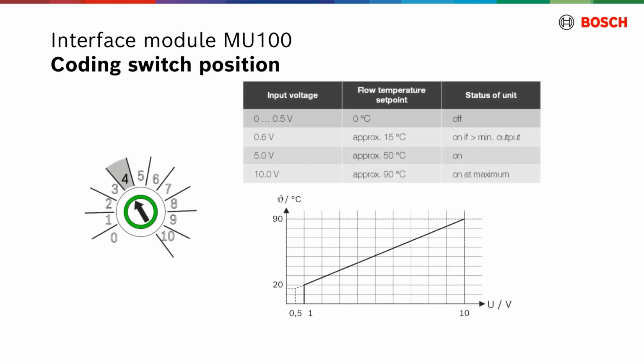With the coding switch in position 4, the module MU100 controls the flow temperature of the boiler. The connected heat source is enabled and disabled according to the signal from BMS and the required flow temperature. There is a linear relationship between the 0 to 10 volt input signal from BMS and the required flow temperature of the boiler. This varies in the temperature range from minimum to the maximum flow temperature set up in the boiler settings, by default from 20 to 90 degrees Celsius.